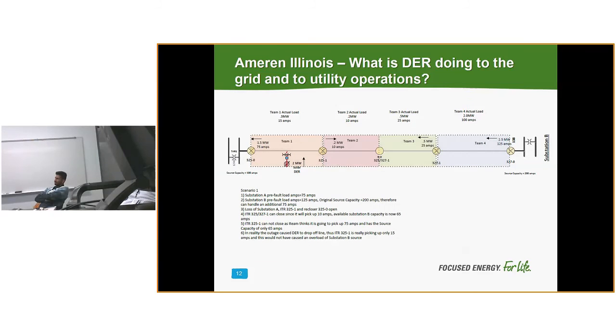This was another example here where I am backfeeding through substation A. So I use the same example, right? The pre-fault conditions are pretty much the same. Just change some of the numbers here. And now this recloser is seeing a 75 amp flow across it. It does not recognize that that 75 amp flow is backflow. That's because my DER is producing enough energy to cover for this, plus it's backfeeding onto the subtransmission.